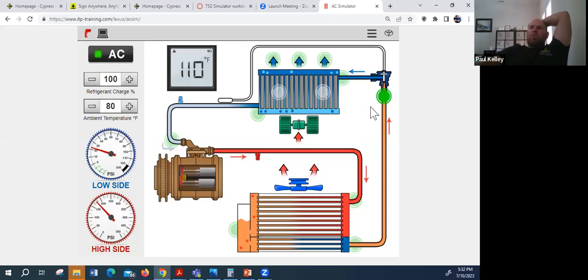You can measure the temperature going into the TXV, coming out of the evaporator, going into the compressor, coming out of the compressor, going into the condenser, at the evaporator, the receiver dryer. You can measure all these places, so just understanding what should be hot and what should be cold is going to be helpful.